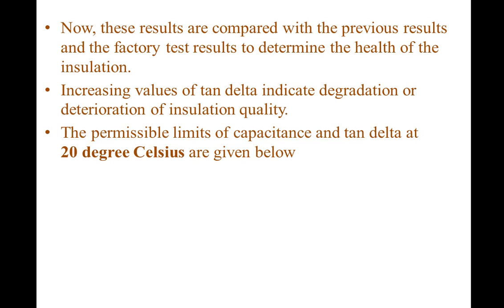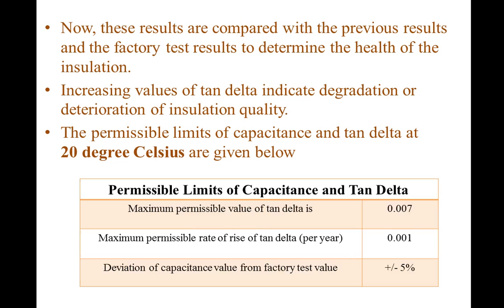The permissible limits of capacitance and tan delta at 20 degrees Celsius are: maximum permissible value of tan delta is 0.007; maximum permissible rate of rise of tan delta per year is 0.001; and the deviation of capacitance value from factory test value should be within plus or minus 5%.